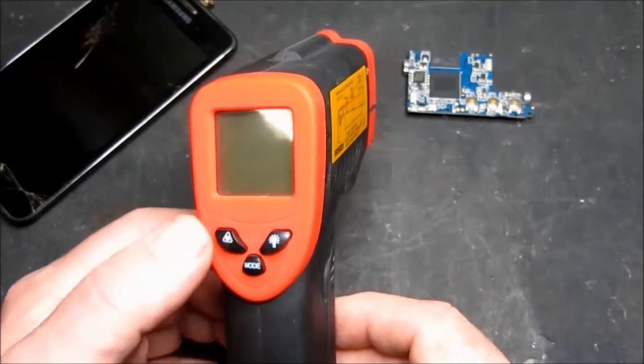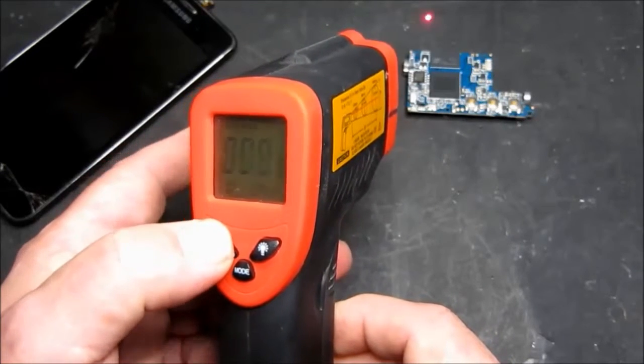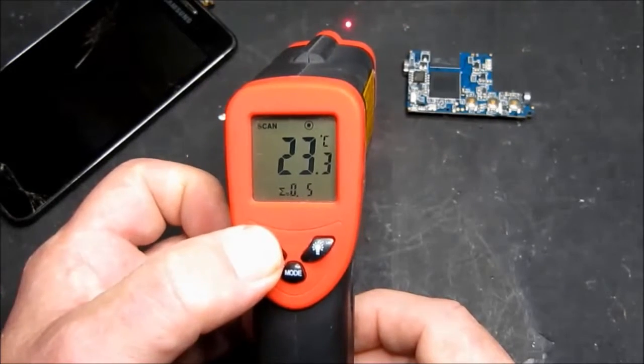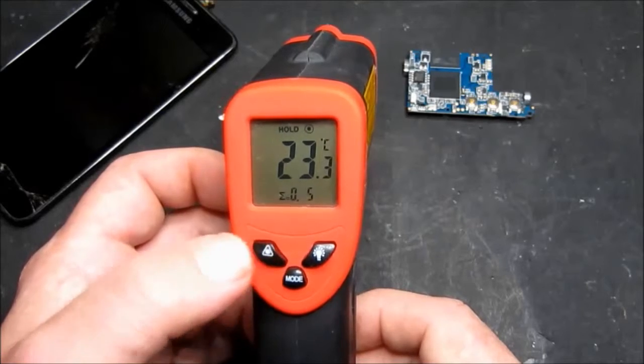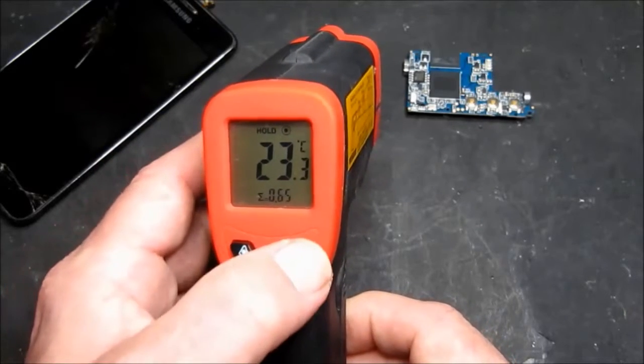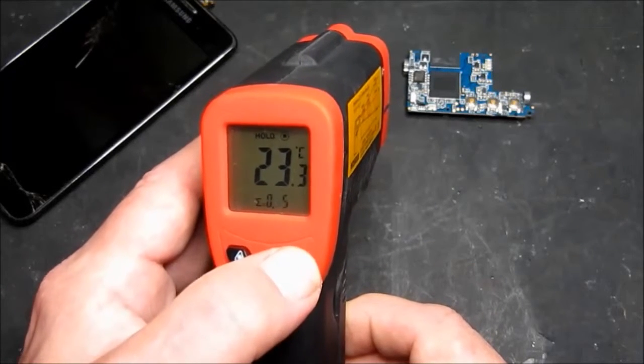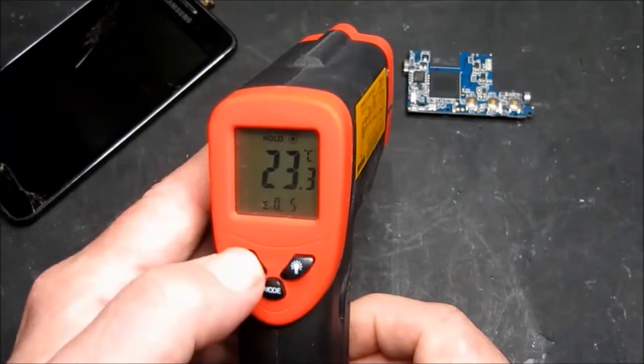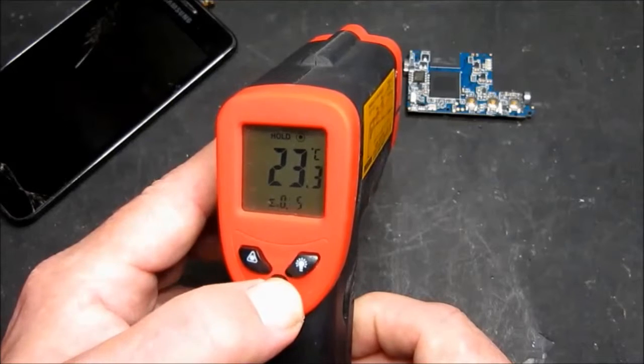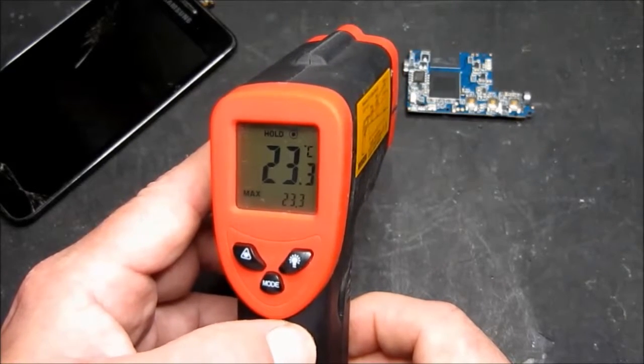So how we do that is we press and hold the laser button whilst we put the trigger on. And there we can see at the bottom of the screen we can now set the emissivity using the laser button or the backlight button just to set that to what we need. So we're going to set that to 0.85 just by pressing the mode key and now the emissivity is set for glass.